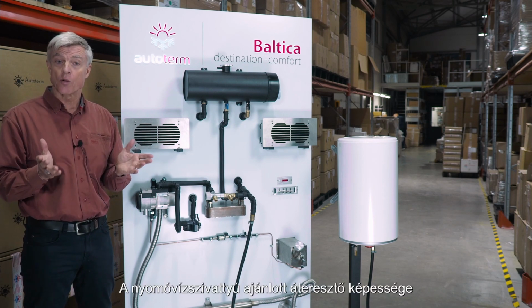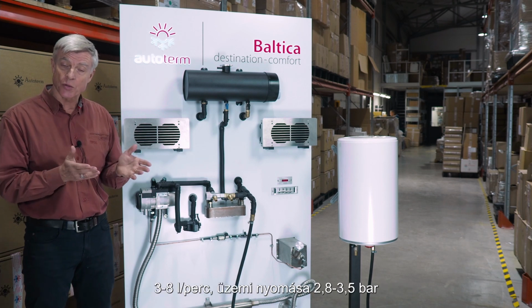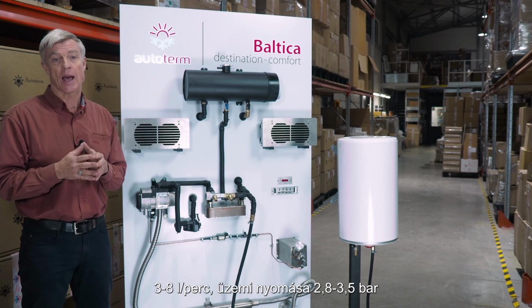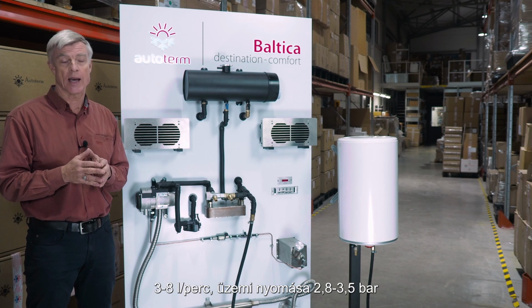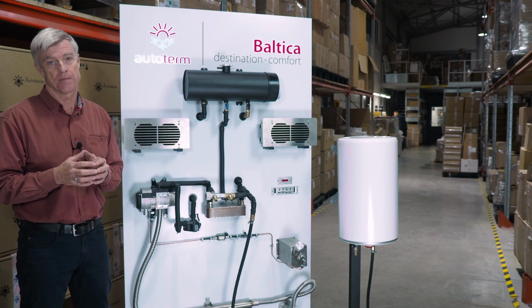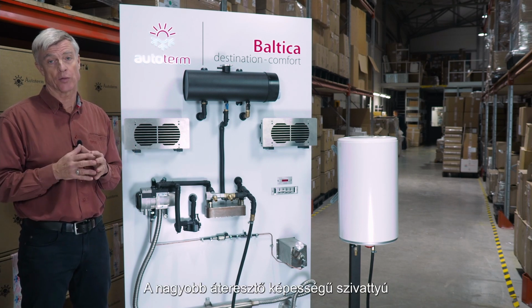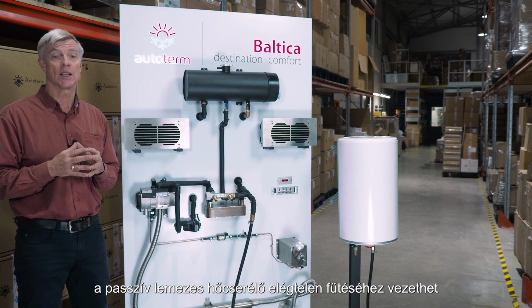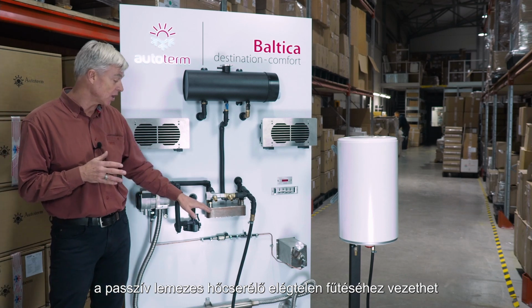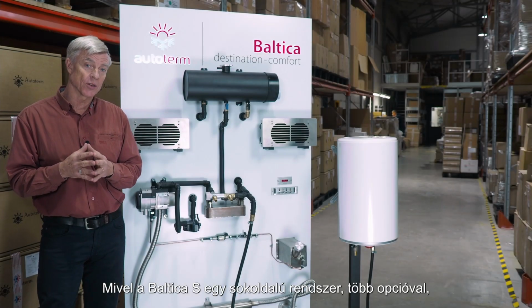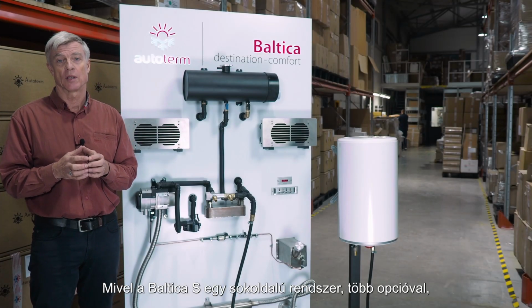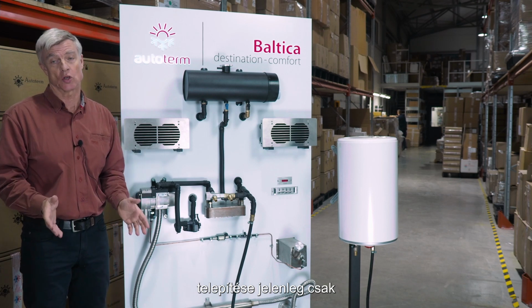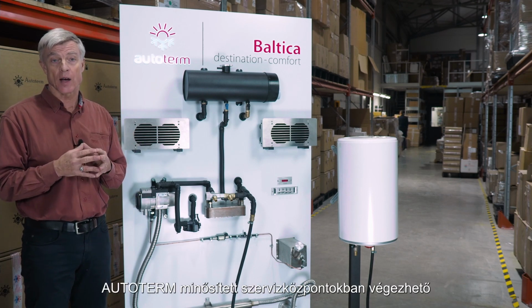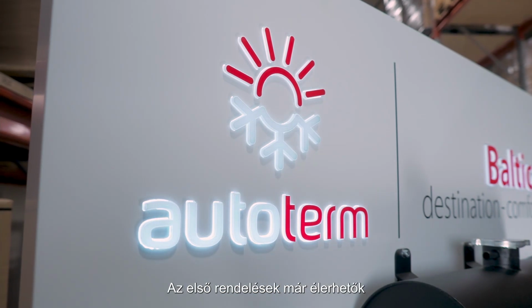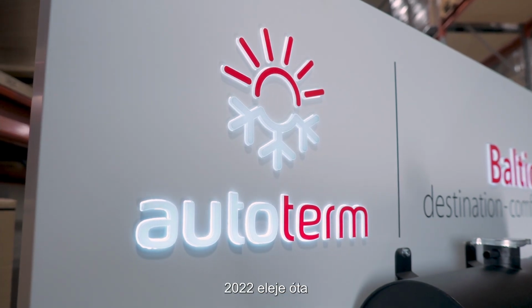The recommended flow through of the pressure water pump is 3 to 8 litres per minute, and the working pressure 2.8 to 3.5 bar. A pump with a higher flow through can lead to insufficient heating of the passive plate heat exchanger. As Baltica S is such a versatile system with multiple options, it's currently only available to install at AUTOTERM certified service centres and will be available for first orders due in 2022.